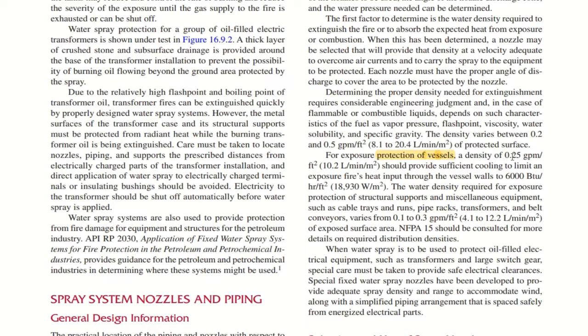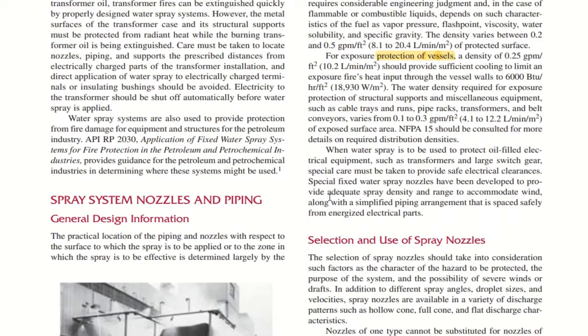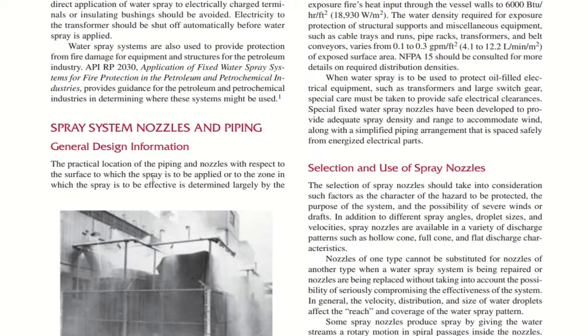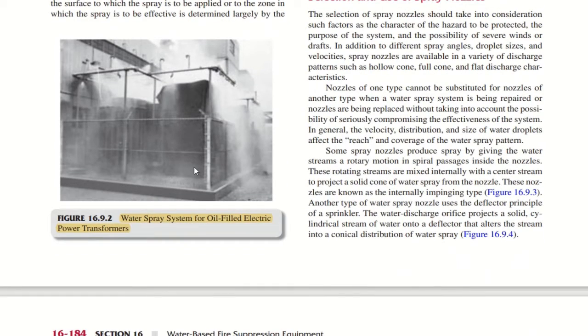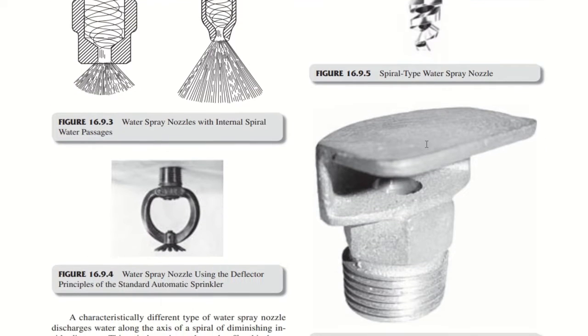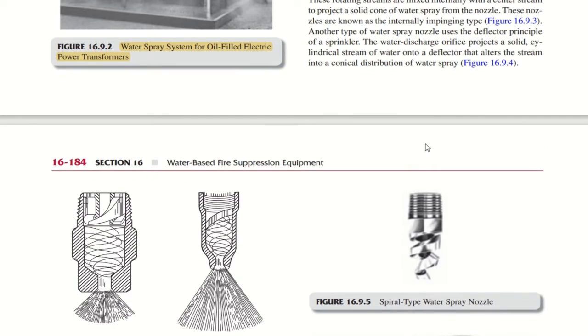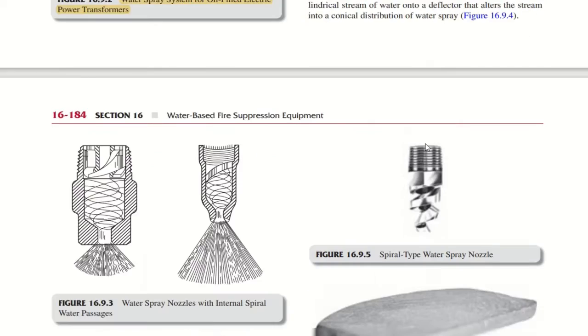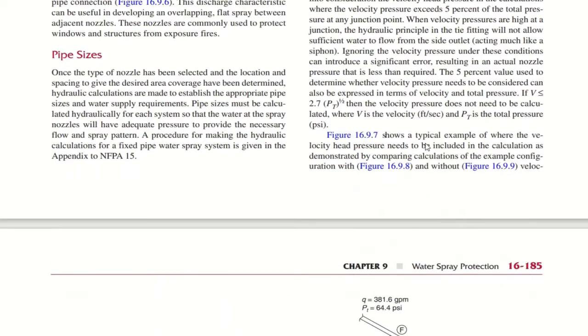For exposure protection of vessels, a density of 0.25 GPM per square foot should provide sufficient cooling to limit an exposure fire's heat input through the vessel walls to 6000 BTU per hour per square foot. NFPA 15 refers to the water spray fixed systems. Here they have shown a figure of a water spray system for oil filled electrical power transformers. So water spray systems are basically used for LPG gas tank protection and electrical power transformers, etc.